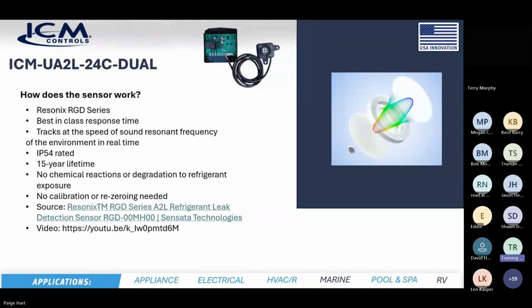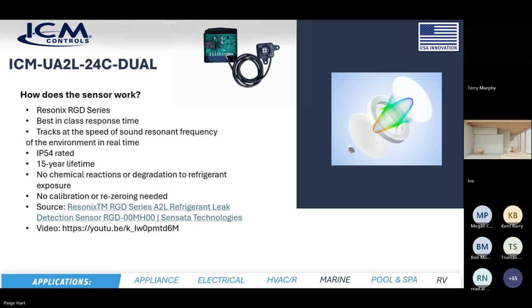So how does the sensor work? Well, the sensor company that we use, which is Sensata, we use what they call the Resonix RGD series, because it's got the best-in-class response time to these A2L refrigerants. And what it does is it's kind of neat. It tracks the speed of sound at a resonant frequency in the environment of this A2L refrigerant. So when the A2L refrigerant leaks into an environment, it changes the way sound travels through that environment. And we can pick up that change with the sensor with very high sensitivity.